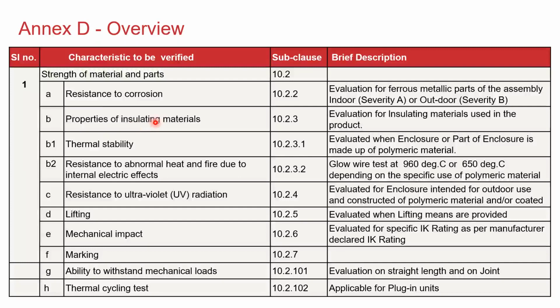Then for all of the insulating materials used in your busways, we have to perform a couple of tests. What are those tests? We have thermal stability, then resistance to abnormal heat and fire, then the UV test. These three tests are essentially for all of the insulating material, depending on whether it is used indoor or outdoor. The first one is thermal stability. If you have an enclosure and you notice that a part of the enclosure is made of polymeric material, then you will have to perform the thermal stability test.